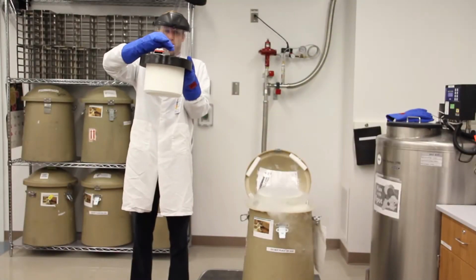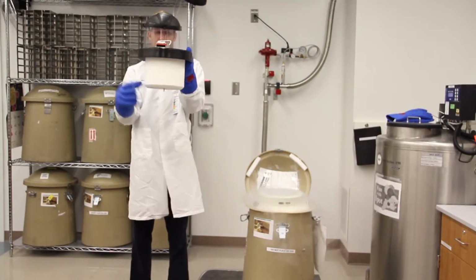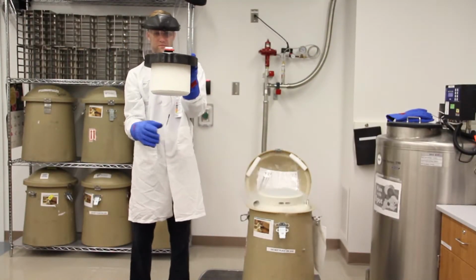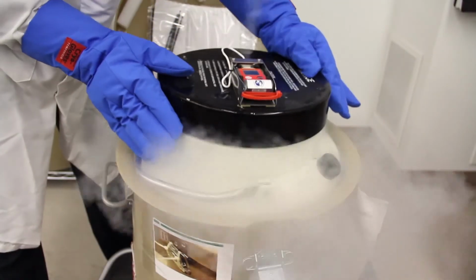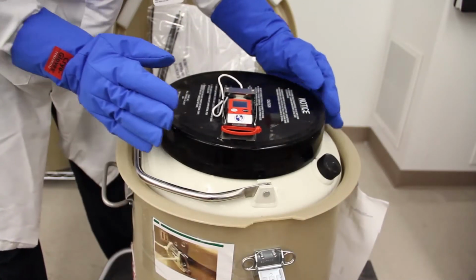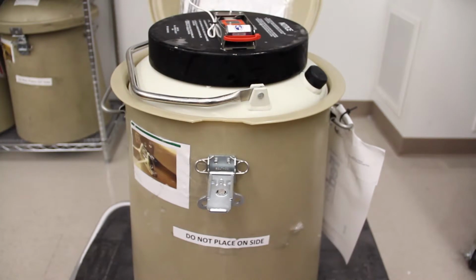Before replacing the black dewar lid, push the temperature probe from the foam as demonstrated. When the black dewar lid is in place, the temperature probe should be unobstructed to allow for proper temperature readings. Now the cryoport is recharged and ready for shipment.